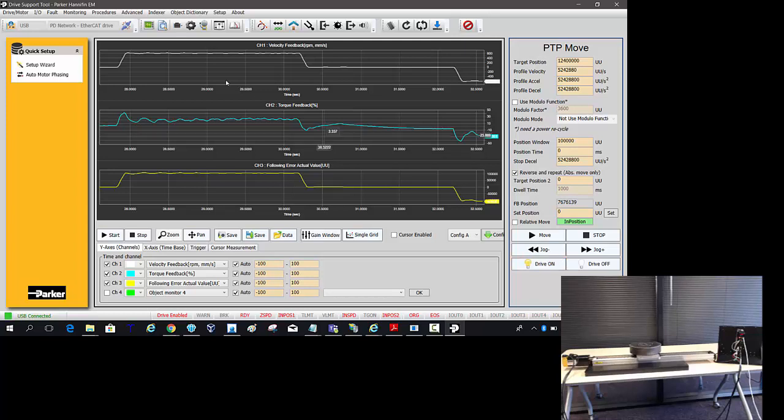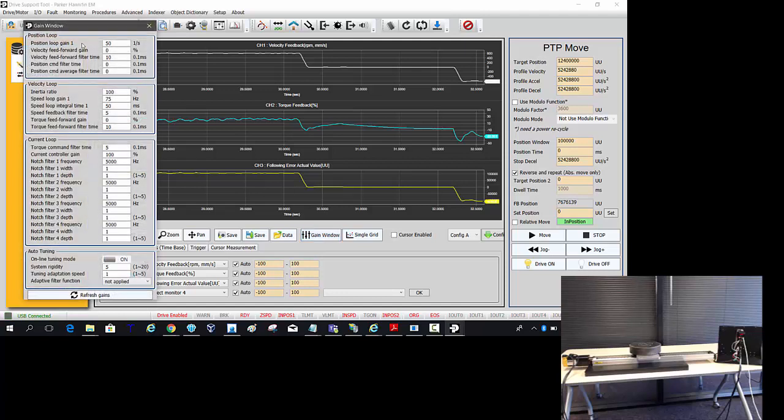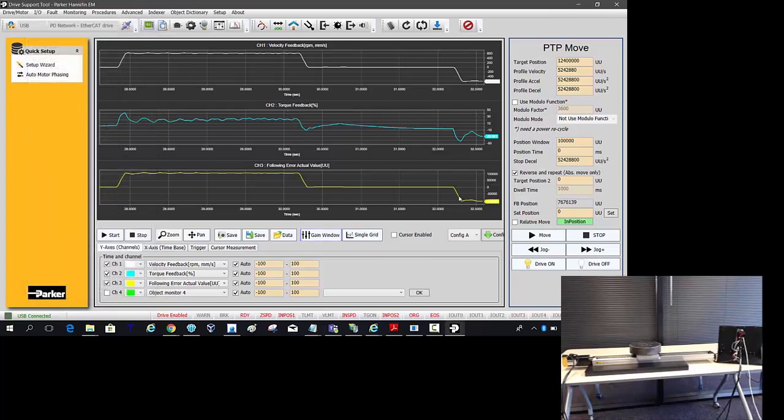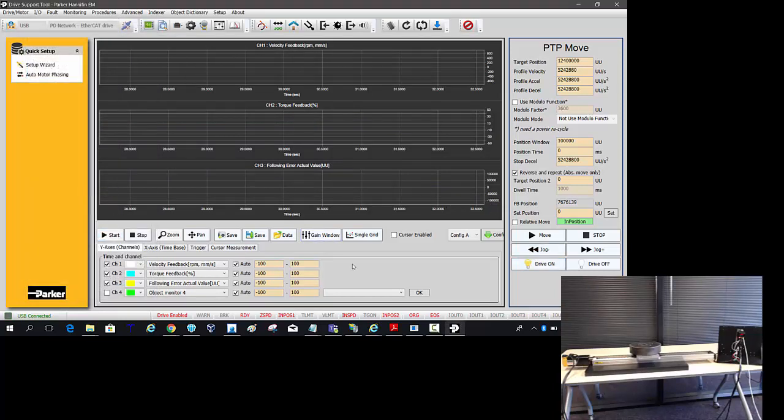So first thing I would do to stiffen that up if I go into the gain window. Take the velocity feed forward gain. And unfortunately the default is 0%. So let's go ahead and set that to 100%. I'm going to start my graph again.